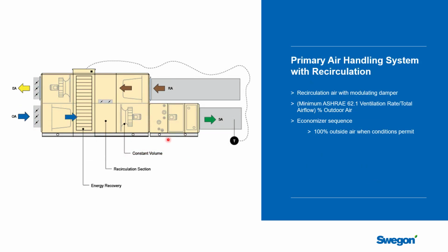Now, another thing that you'll often see in a unit is that they'll add a recirculating section into the unit. So it's not unusual for a chilled beam system to supply more primary air to the building than the actual outdoor air requirement as per, say, ASHRAE Standard 62.1. So in an office space, 62.1 is somewhere around 0.1 to 0.15 CFM a square foot. It's not unusual to see a chilled beam system designed at 0.3 CFM a square foot.